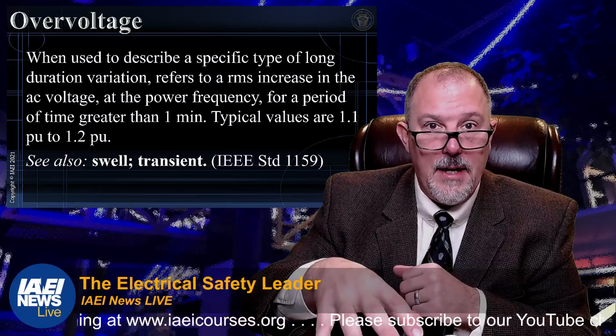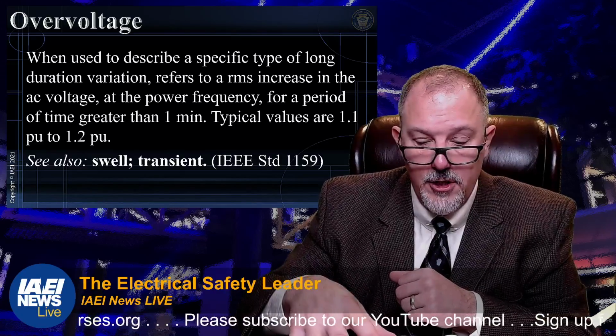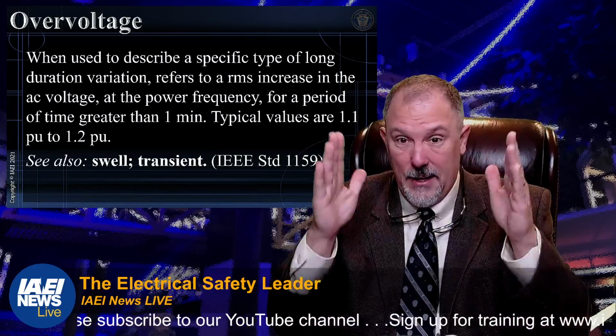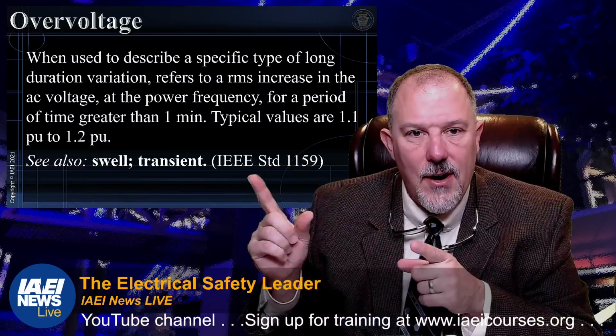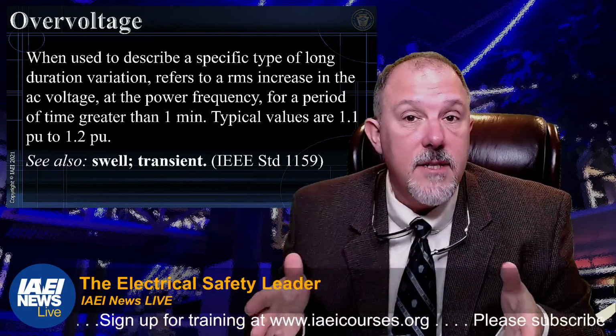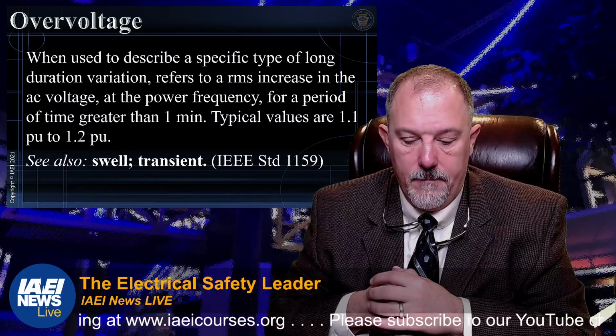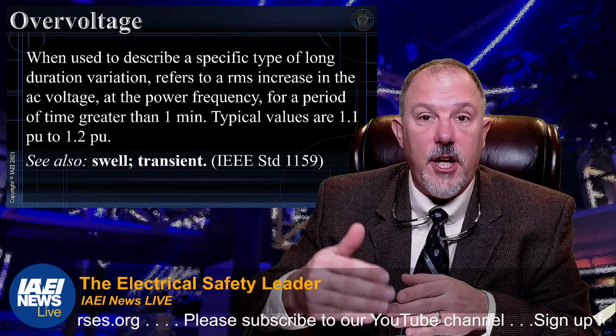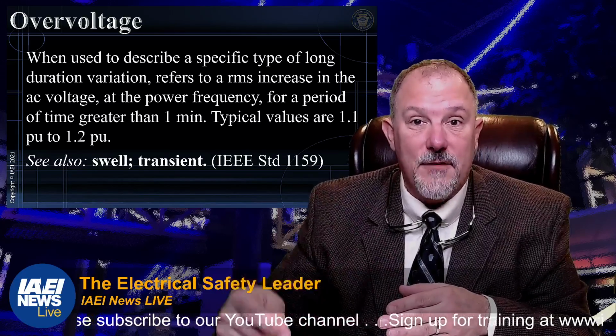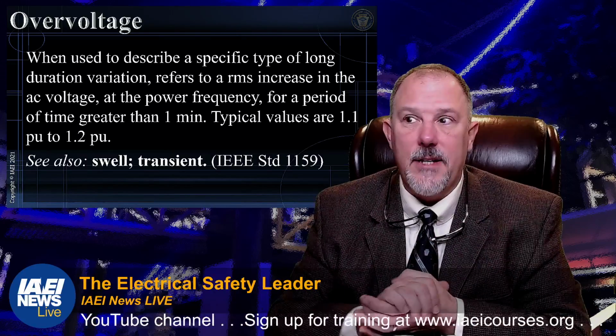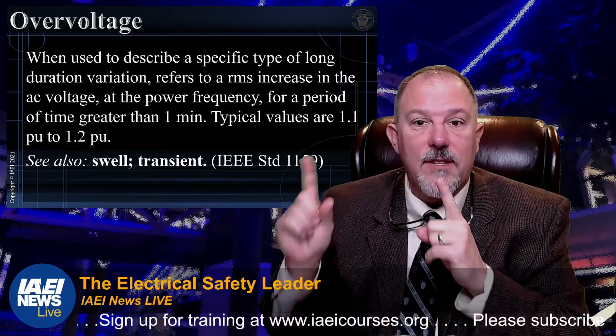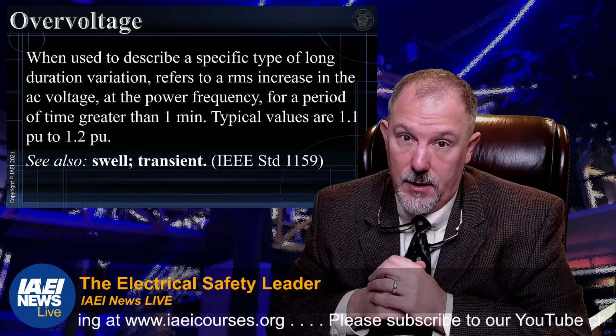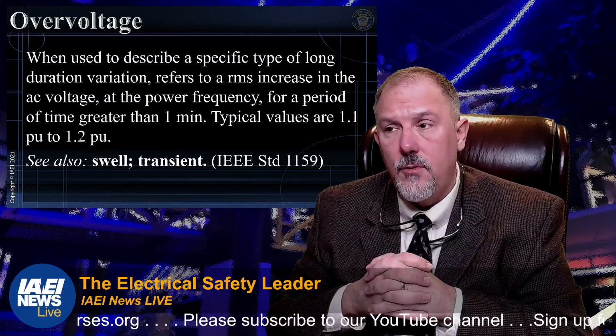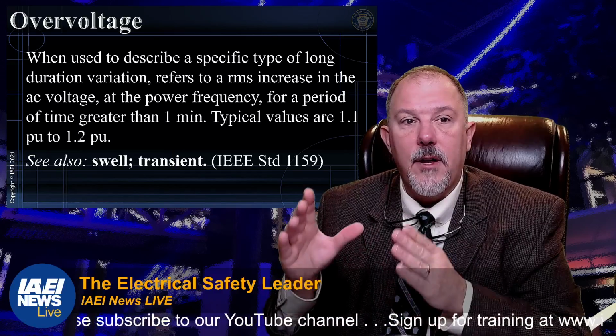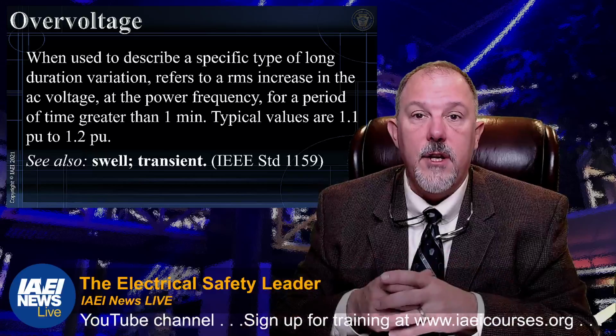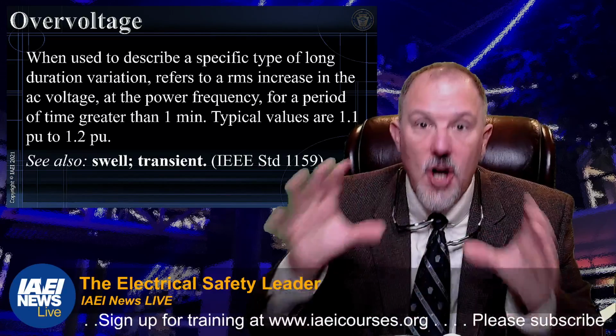And the code has introduced Article 242 called overvoltage protection. And in my mind, I've got to reconcile that. I have to think, this is how I was taught. I know what an overvoltage is. And when we had this discussion at the table, because there were public inputs and comments seeking to change surge protection device to an overvoltage protection device, those around the table in panel 10 said, no, that does not make sense. Why? Because of these terms, and these terms have been used for years. So you have a group of engineers and others who have been taught voltage protection and taught that this is what an overvoltage is. This is what a voltage swell is. This is what a voltage transient is. And this is what a voltage notch is, right?